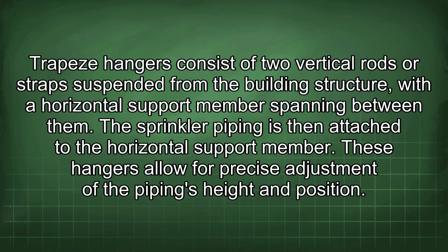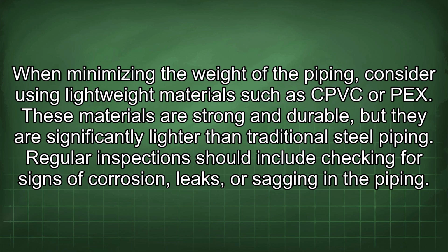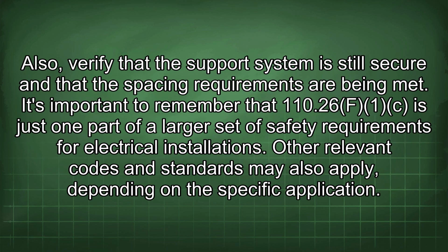equipment. Trapeze hangers consist of two vertical rods or straps suspended from the building structure with a horizontal support member spanning between them. The sprinkler piping is then attached to the horizontal support member. These hangers allow for precise adjustment of the piping's height and position. When minimizing the weight of the piping, consider using lightweight materials such as CPVC or PEX. These materials are strong and durable, but they are significantly lighter than traditional steel piping. Regular inspections should include checking for signs of corrosion, leaks, or sagging in the piping. Also, verify that the support system is still secure and that the spacing requirements are being met.